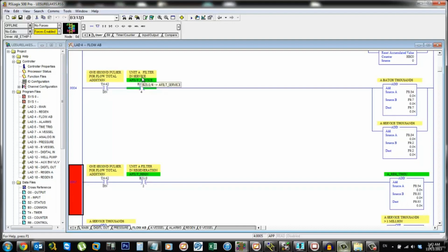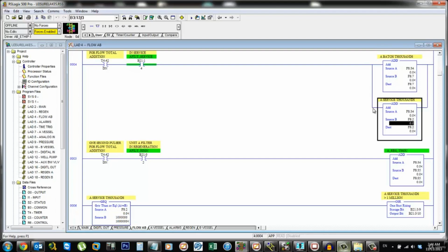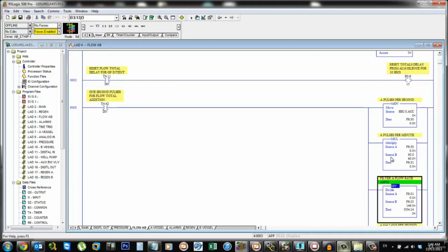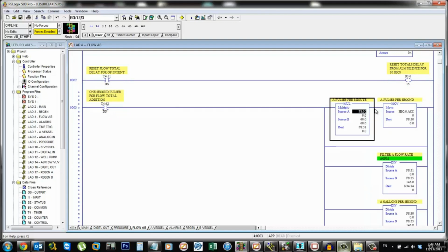So if you don't take anything else out of this lecture, the one thing you have to understand and can't forget from here going forward, this is the one thing that makes ladder logic make sense: what you see on the left are conditions. What you see on the right are actions. And for each branch, you have one action. If we want multiple actions to come out of this rung, we have to put each action on a separate branch. What we cannot have is 2 actions on the same branch.